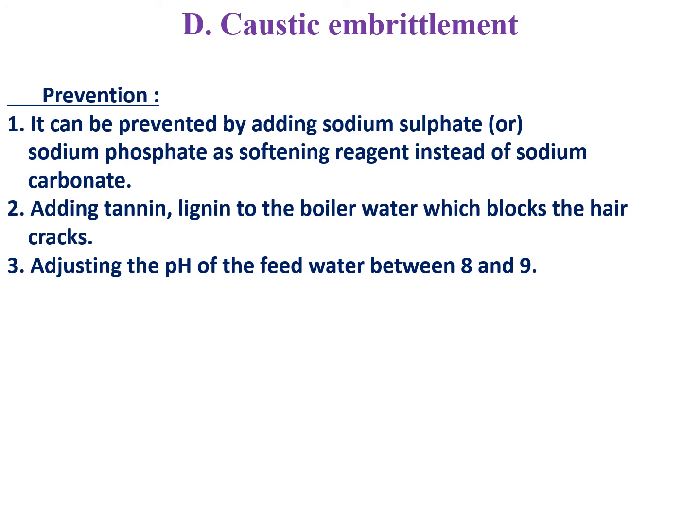By adjusting the pH to 8–9, you can avoid caustic embrittlement. NaOH has a high pH (up to 13–14), so keeping the pH in the 8–9 range prevents it. In caustic embrittlement, a concentration cell appears because NaOH concentration differs between the outer and inner sides of the boiler, leading to differential aeration-type corrosion — creating pits, cavities, and holes (pitting corrosion), causing severe damage to the plant. This concludes the topic of boiler corrosion and caustic embrittlement. Please subscribe to my channel — thank you for watching.